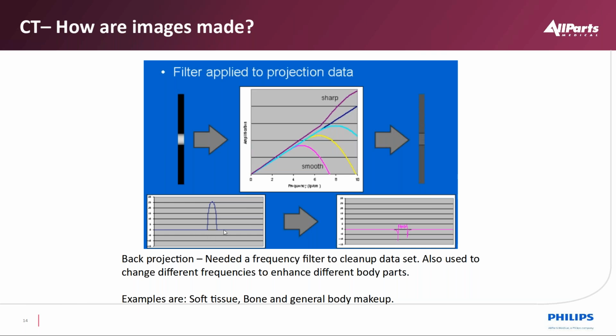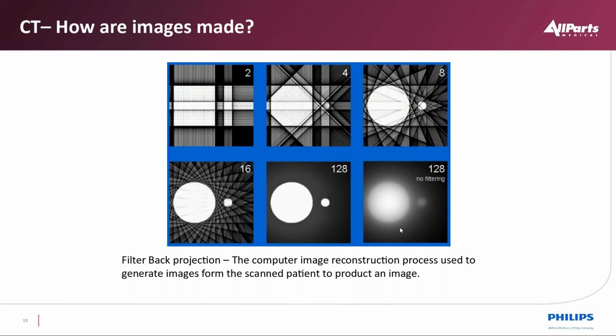So we basically take this data set, run it through a frequency filter, a fast Fourier transform, and then we do an inverse fast Fourier transform to have what the data set would look like here. So this inherent artifact introduction is these negative going spikes that were never in the data, but they still show up in the image. And here you see the light edge of basically dark or black lines that wasn't originally in the image. But that's part of the image artifact that's known to be part of CT image reconstruction, inherent artifacts. So with a filter applied, before we even project the data back, we filter it first.